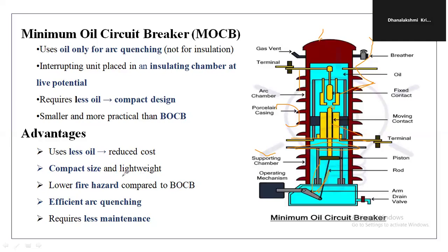So some advantages are there. It uses very little oil, so it reduces the cost. It is compact in space and lightweight. There is a reduced risk of fire and efficient arc quenching. It requires less maintenance.